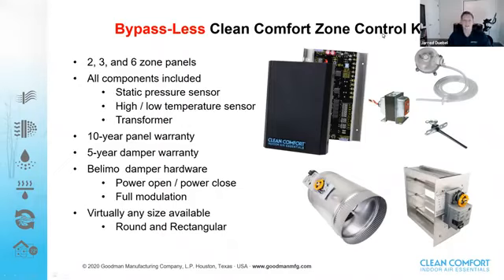So if you can see here in the picture, all of these zone control systems we're going to offer in a kit. So we make sure that you're going to get everything that you need out in the field specifically for that job. It's going to obviously include your zone control panel, your transformer, so you can have it on its own isolated circuit, the static pressure sensor, which is going to come with all the bypass-free zone control systems, and then a discharge temperature sensor if you would like to make use of that to trip the high and low limits in the system.